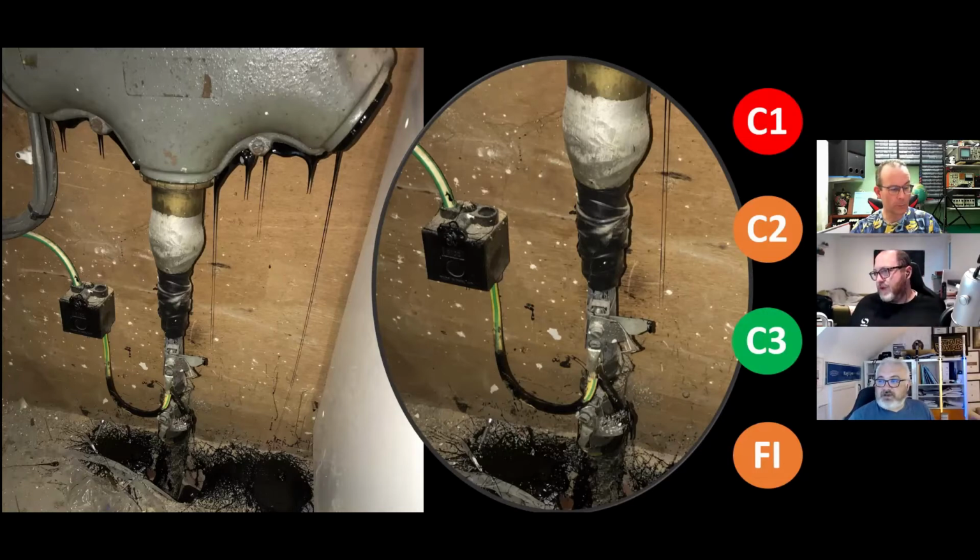So has everyone coded it yet? We've got pretty much 80% who have had a go. 63% have gone C2. Oh no, Daniel Casey has put what looks like TNS. Correct, you are correct. If I was looking at that on the electrical installation certificate, I would absolutely put that as a TNS service head. There is no doubt in your mind. It's clearly TNS. The configuration of it is TNS. It's just leaking pitch, which is horrible and disgusting.